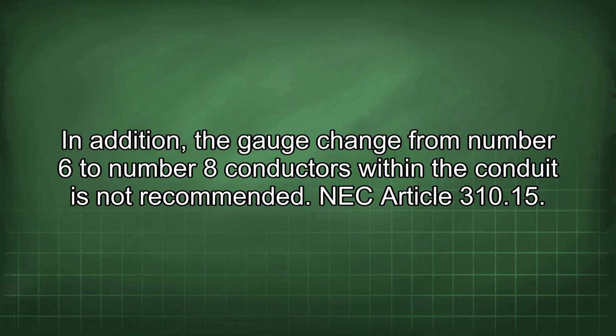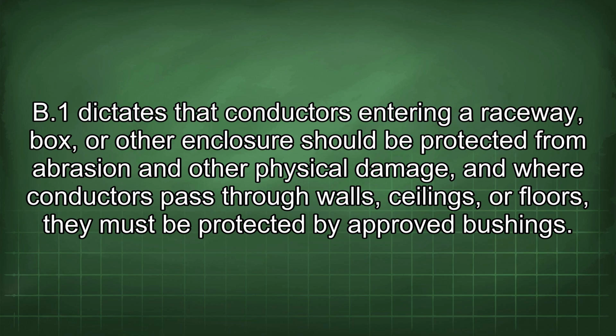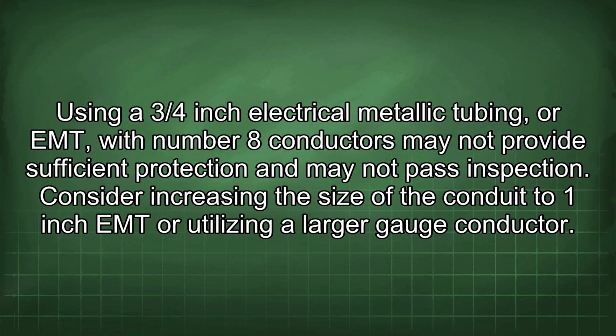In addition, the gauge change from number 6 to number 8 conductors within the conduit is not recommended. NEC Article 310.15.B.1 dictates that conductors entering a raceway, box, or other enclosure should be protected from abrasion and other physical damage, and where conductors pass through walls, ceilings, or floors, they must be protected by approved bushings. Using a 3/4-inch electrical metallic tubing, or EMT, with number 8 conductors may not provide sufficient protection and may not pass inspection. Consider increasing the size of the conduit to 1-inch EMT or utilizing a larger gauge conductor.